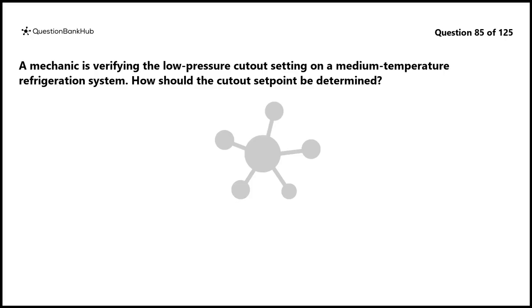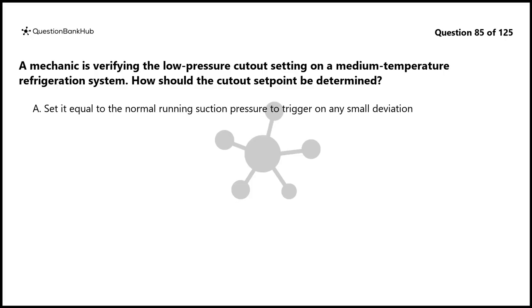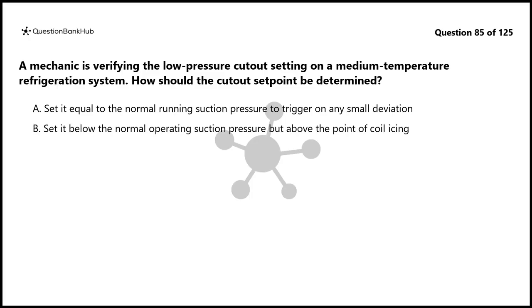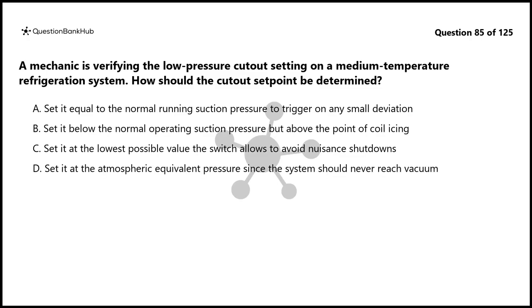Question 85. A mechanic is verifying the low-pressure cutout setting on a medium-temperature refrigeration system. How should the cutout set point be determined? A. Set it equal to the normal running suction pressure to trigger on any small deviation. B. Set it below the normal operating suction pressure but above the point of coil icing. C. Set it at the lowest possible value the switch allows to avoid nuisance shutdowns. D. Set it at the atmospheric equivalent pressure since the system should never reach vacuum.